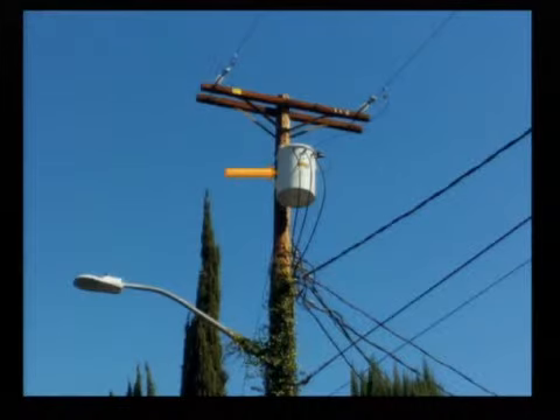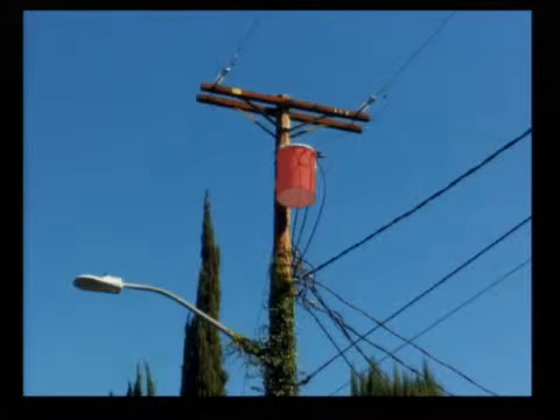Now, in the electric industry, there's two major problems we have with these pieces of equipment. One, that it's underloaded or underutilized. And that might not seem like a problem, but an underutilized transformer is wasting energy every day, and over the lifetime of that transformer, that's a lot of wasted costs we don't want to incur as a utility. The other big problem is an overloaded transformer, one that's pushed beyond its limits. And the reason that's a problem is because it increases the risk of failure that could cause outages for our customers. In the utility industry, we want our transformers to be sized just right. And that's a tall order. What I want to do now is take you through our journey to finding out how to make sure our transformers are sized just right.